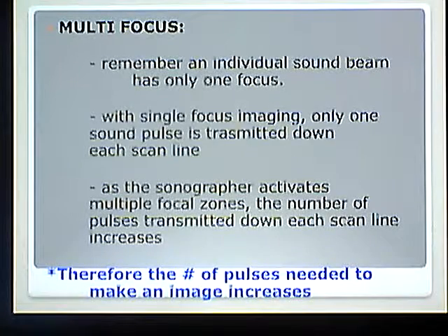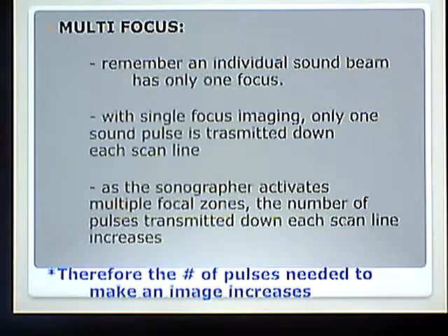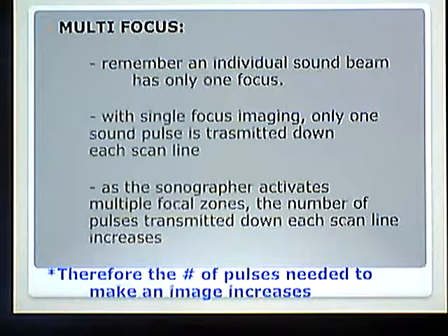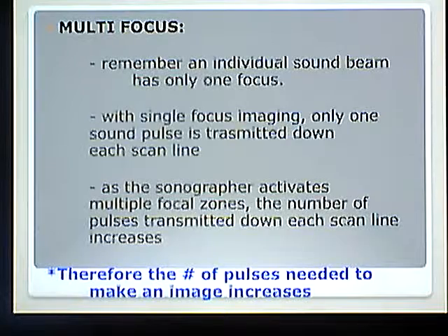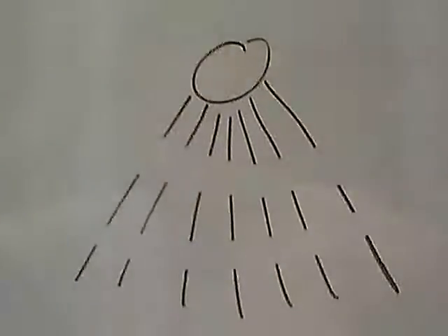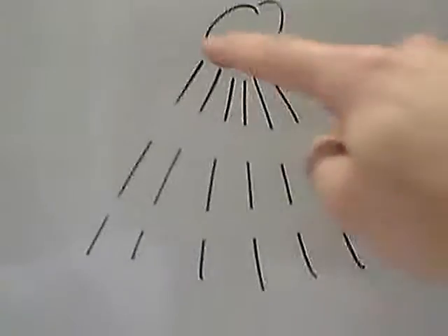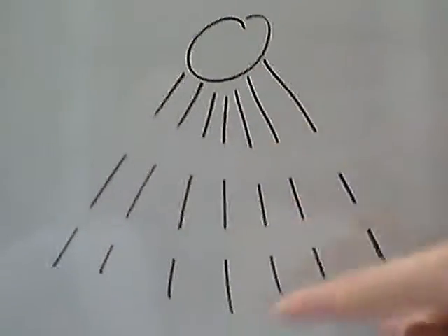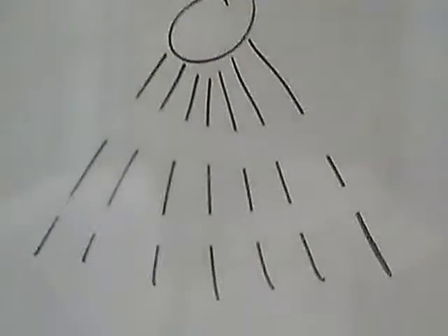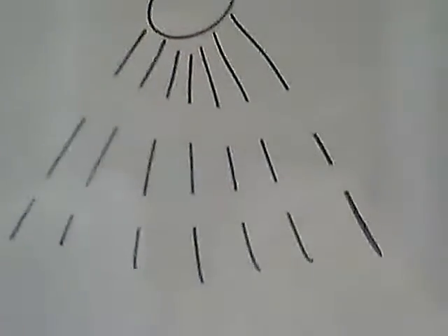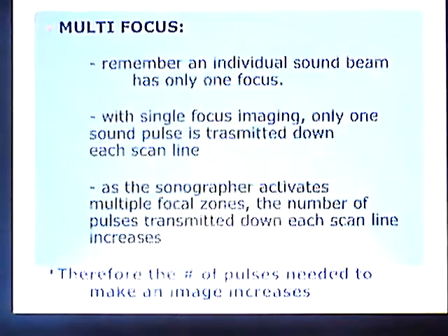As the sonographer activates multiple focal zones, the number of pulses transmitted down each scan line increases. If I have one focus but I want to increase it to three, I now have to send three pulses down each scan line. So instead of before when I had seven scan lines, I now have 21 pulses that I need to use to create that image.